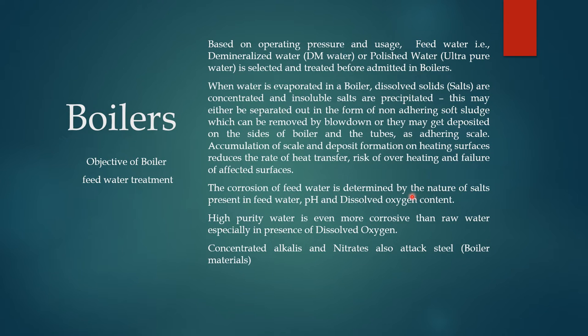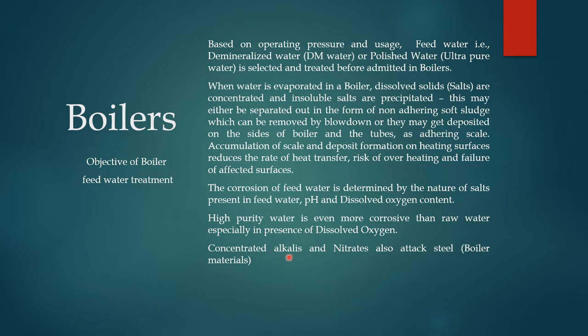Corrosion of feed water is determined by the nature of salts present, the pH of the water, and the dissolved oxygen content. High purity water like DM water or polished water is more corrosive than raw water, especially in the presence of dissolved oxygen — so if oxygen is present in boiler feed water, it is highly corrosive. We must remove dissolved oxygen. Concentrated alkalis or nitrates in boiler feed water will also attack the steel or boiler material, so chemical dosing is required.